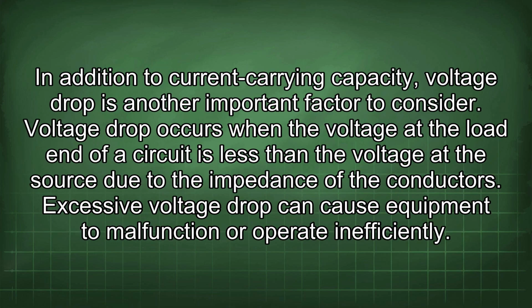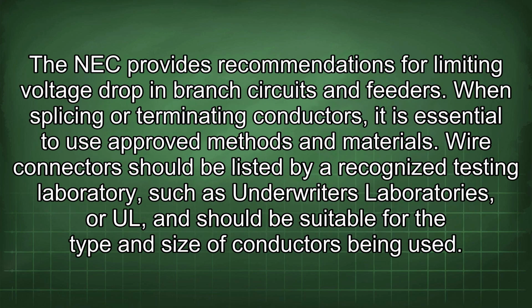In addition to current carrying capacity, voltage drop is another important factor to consider. Voltage drop occurs when the voltage at the load end of a circuit is less than the voltage at the source due to the impedance of the conductors. Excessive voltage drop can cause equipment to malfunction or operate inefficiently. The NEC provides recommendations for limiting voltage drop in branch circuits and feeders.